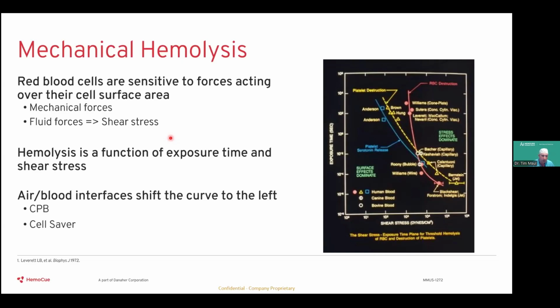One researcher back in the 70s combined the results of a series of published studies to develop a Leverett curve for red blood cells, platelets, and white cells. What you can see when you combine all of the various animal, in vitro, and in vivo data is that there are isolines for each of the cell types, red cells, platelets, or white blood cells, where you plot the shear stress that the cells are exposed to against the time of exposure. Anything to the right of any of these lines, the cells will be basically ruptured or damaged because of the shear stresses. And anything to the left of the lines means that the surface effects, things like surface chemistries or surface roughness, will be the thing that would potentially cause the cells to rupture. So basically, we do not want to live on this side of the curve when we're interacting with patient blood.